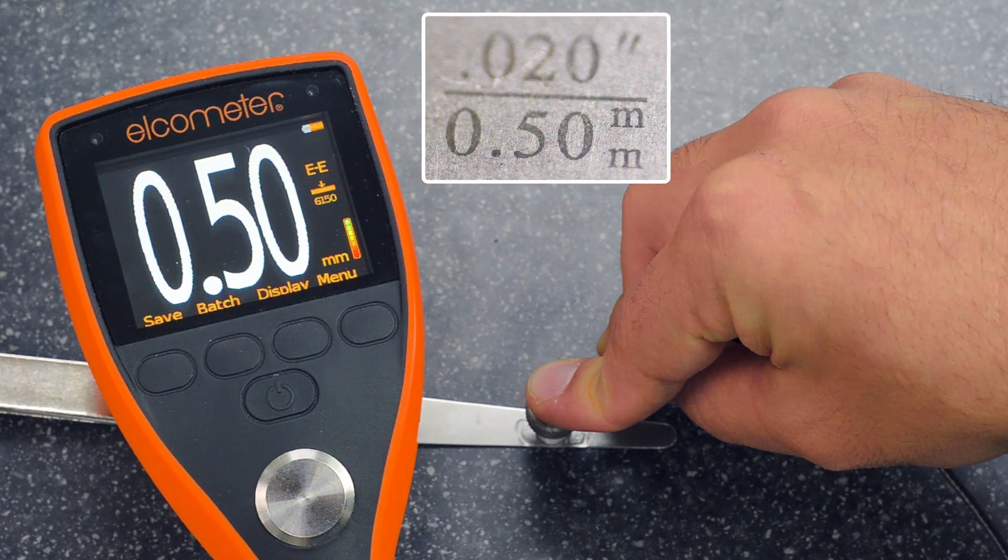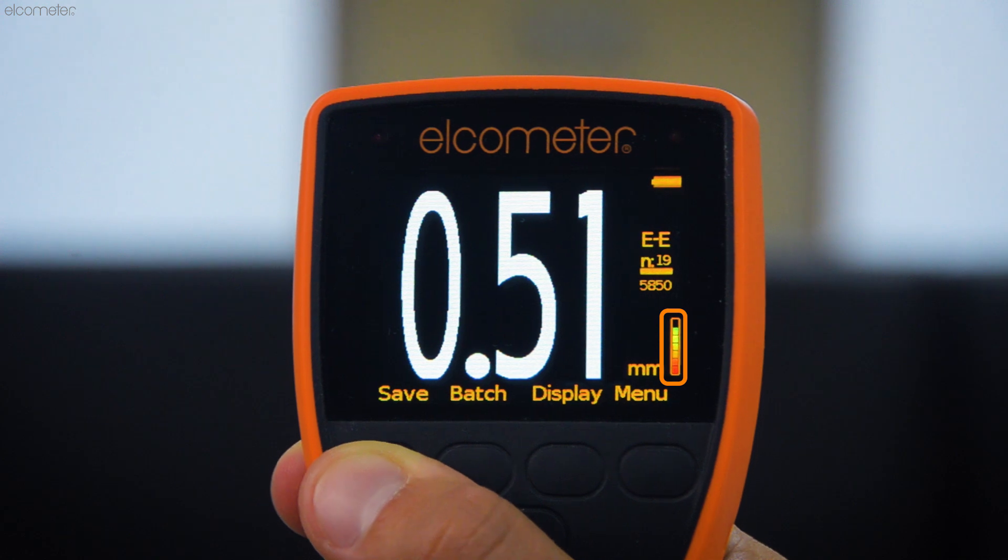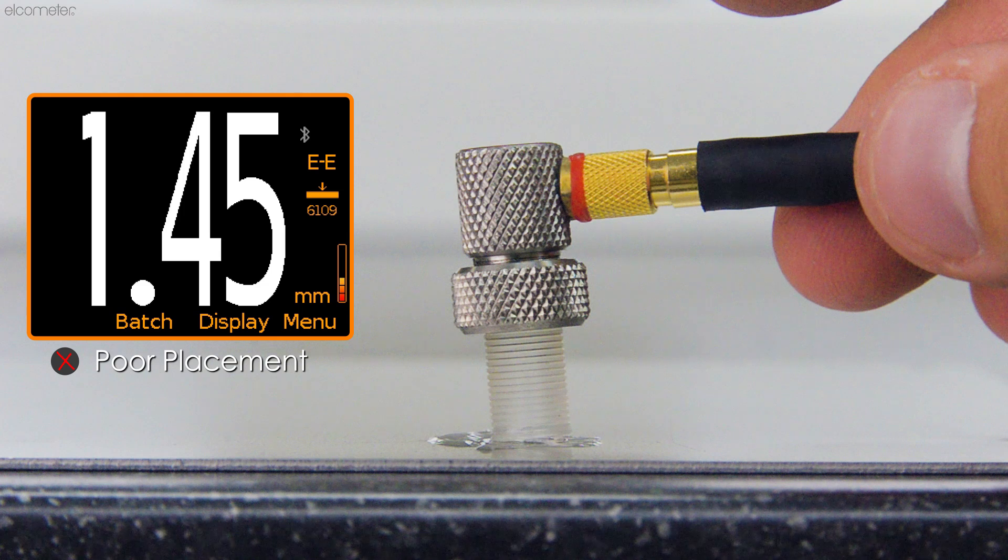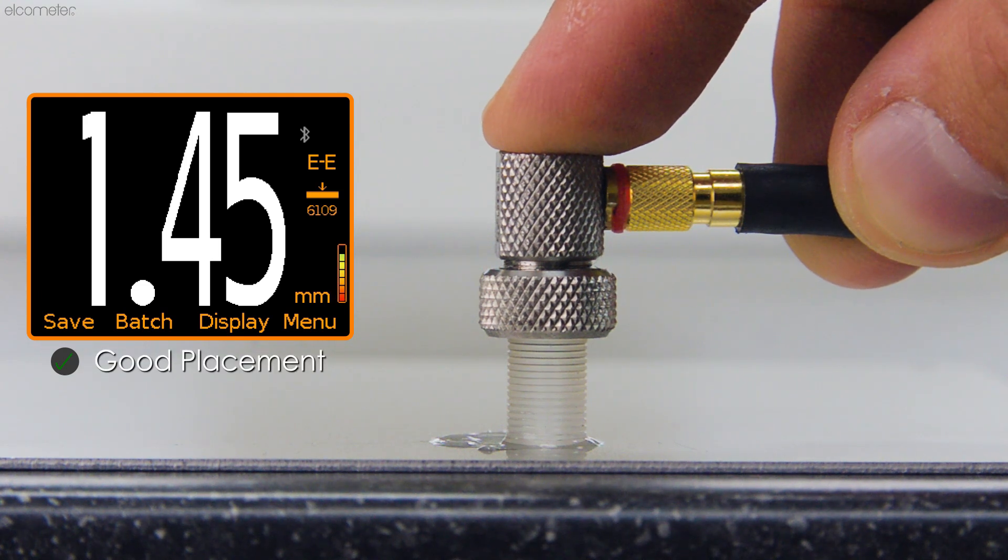When the transducer is placed on the material, the reading stability indicator shows how strong the ultrasonic signal is. A red or orange bar means you may need to adjust how you're holding the transducer or where on the material you're placing it, while a full bar means a strong signal, ensuring accurate, reliable measurements.